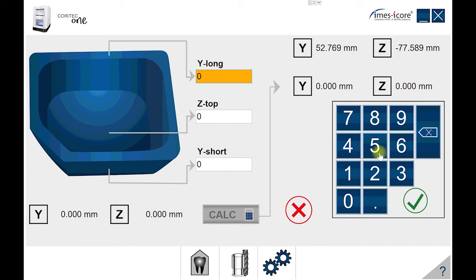The next measurement to take is the Y-short measurement. This is the side of the object that has the angled wall on it. Measure this wall 3 times as well and enter in the measurement. Finally, you will measure the Z-top measurement. Since the calipers you have been supplied with won't measure this thin top wall properly, we will use a calculation to get the proper measurement.